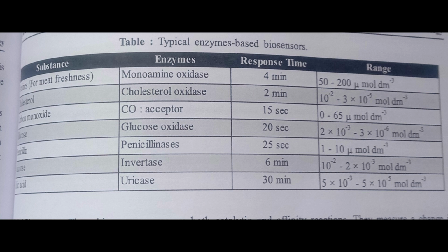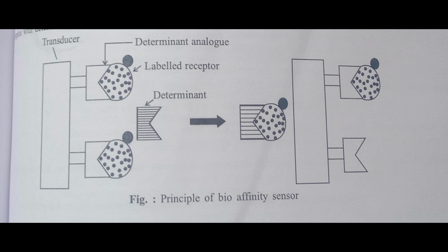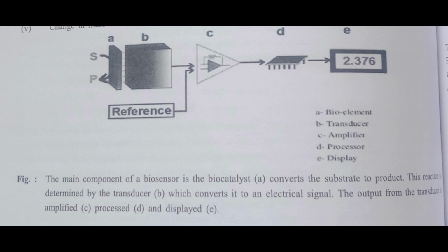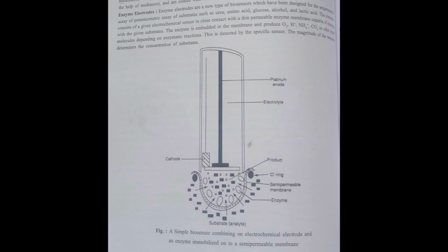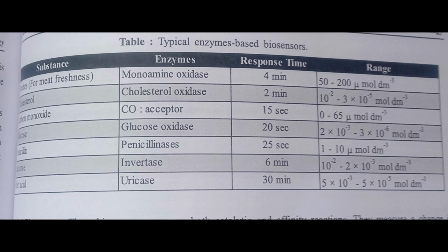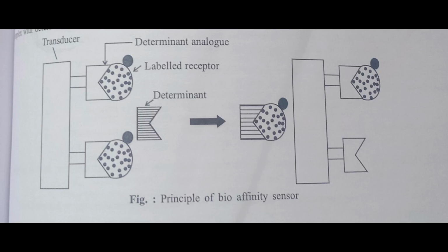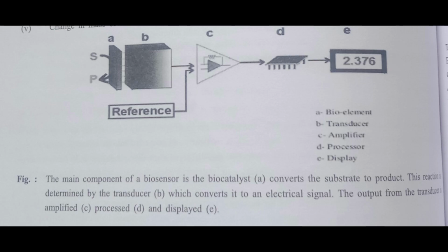The enzymes are usually immobilized by glutaraldehyde on a porous sheet like lens tissue, paper, or nylon net fabric. The enzyme membrane so produced is affixed to the transducer. Generally, correct immobilization of enzyme enhances their capability, which may be rather dramatic in some cases. As a result, many enzyme immobilized systems can be used more than 10,000 times over a period of several months.